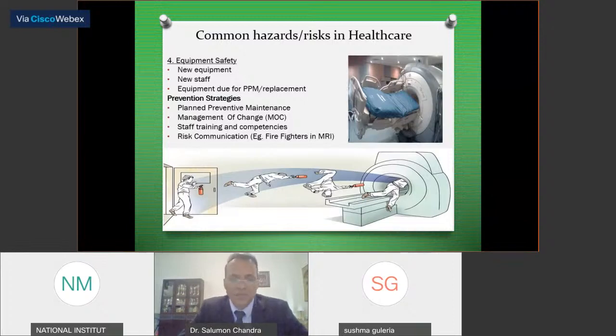During the investigation, it was revealed that since this ventilator was out of the MRI for quite some time, during one of the planned preventive maintenance sessions, the biomedical engineers replaced the MRI-compatible battery with a ferromagnetic battery. For them, since it was never used in MRI, they assumed it never would be, so that message was not communicated. That was the lesson learned.